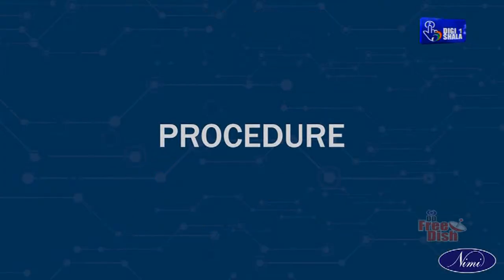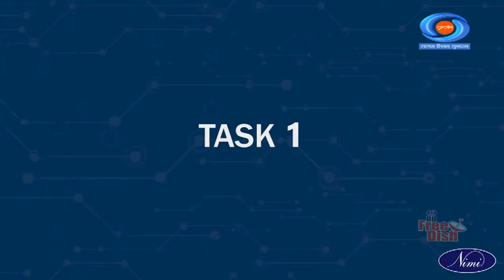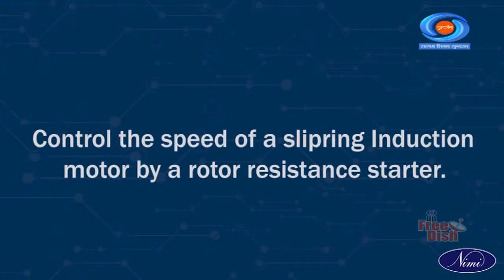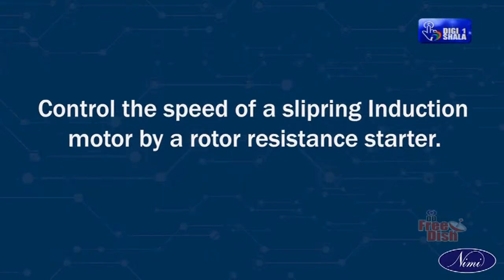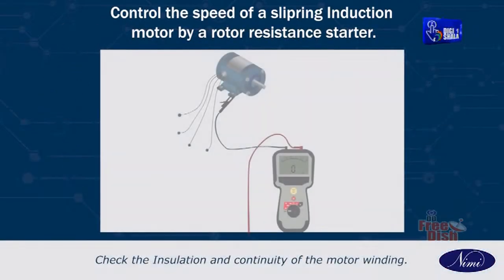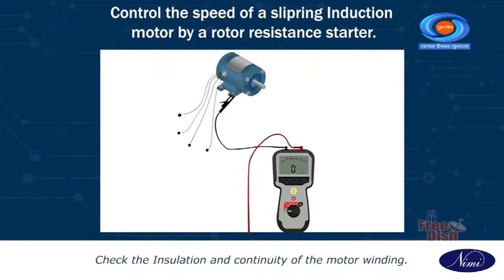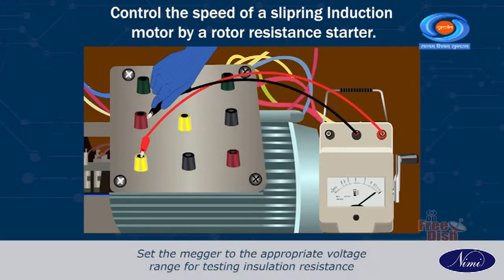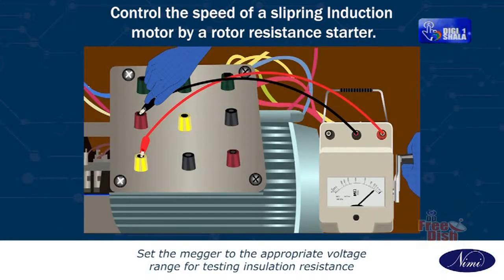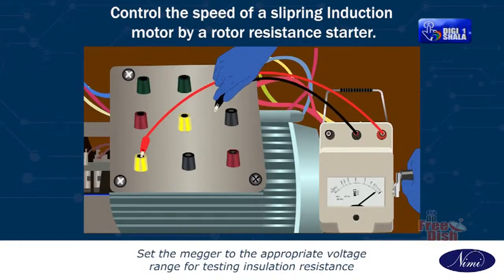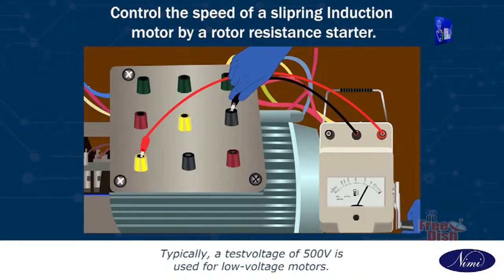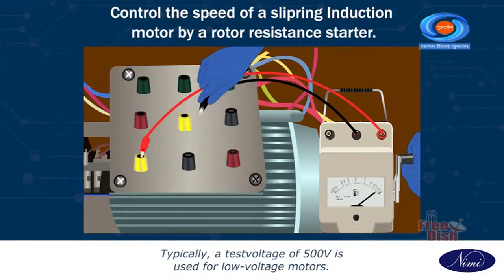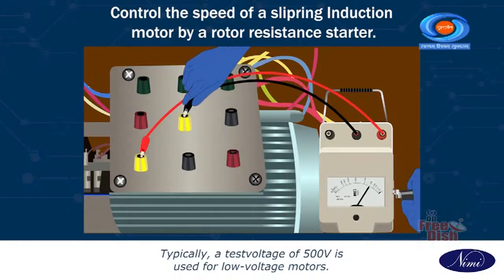Procedure. Task 1. Control the speed of a slip ring induction motor by a rotor resistance starter. Check the insulation and continuity of the motor winding. Set the megger to the appropriate voltage range for testing insulation resistance. Typically, a test voltage of 500 volt is used for low voltage motors.